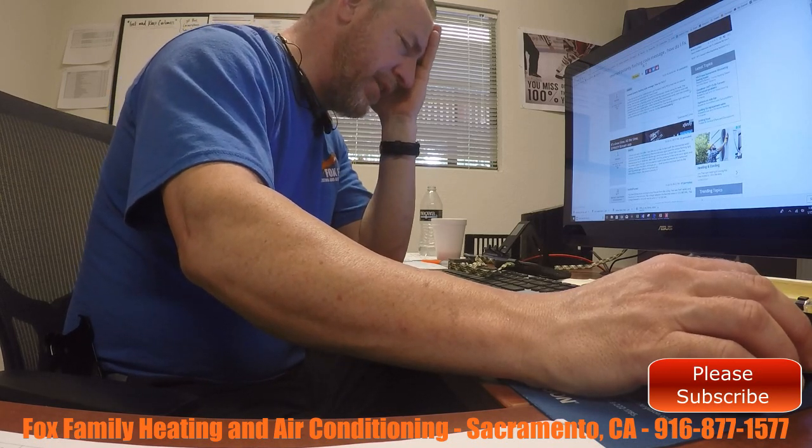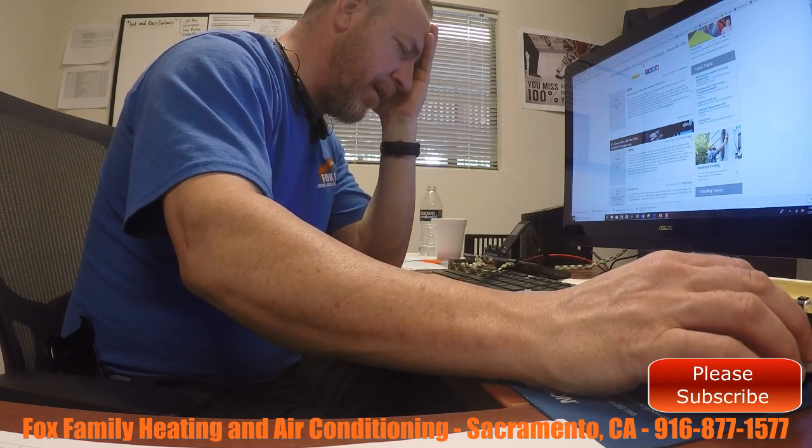The rain, is there any chance that it got into the flue pipe and then fell out of the inducer assembly or something? I wouldn't suggest so, because I didn't see any water in the burner compartment. It's just in the blower compartment? Yeah, there's just water there.